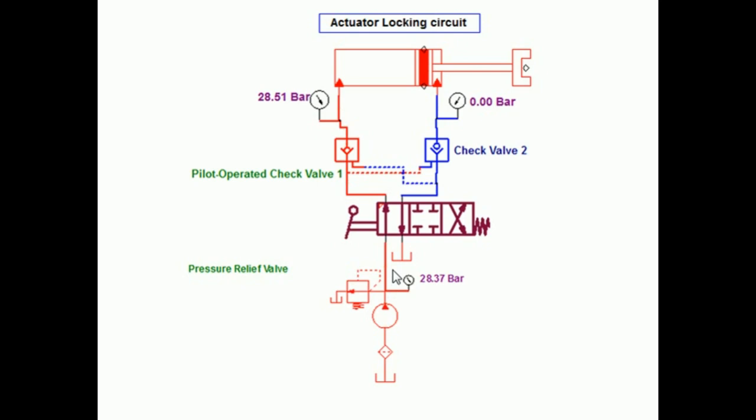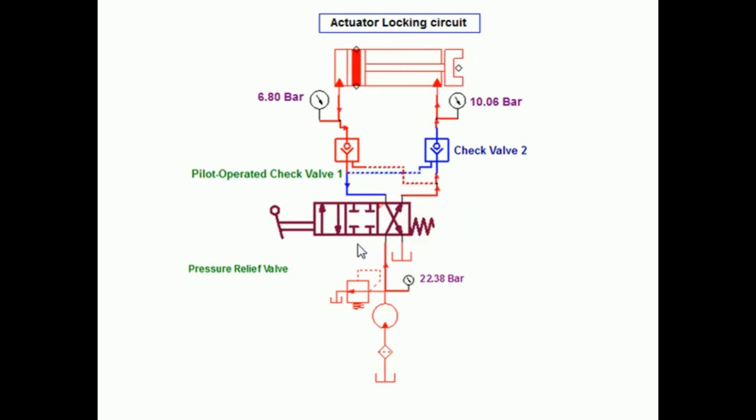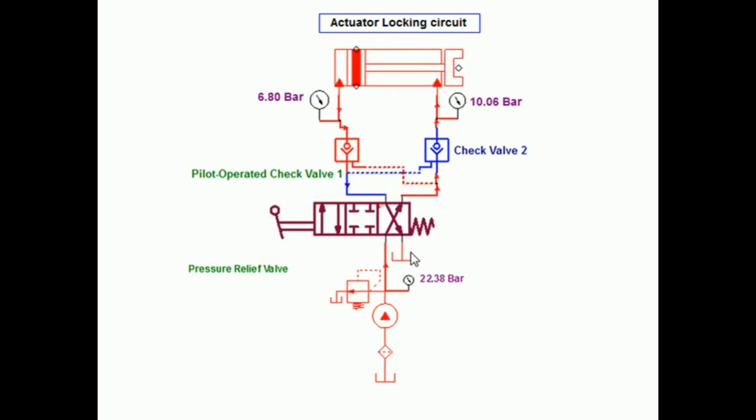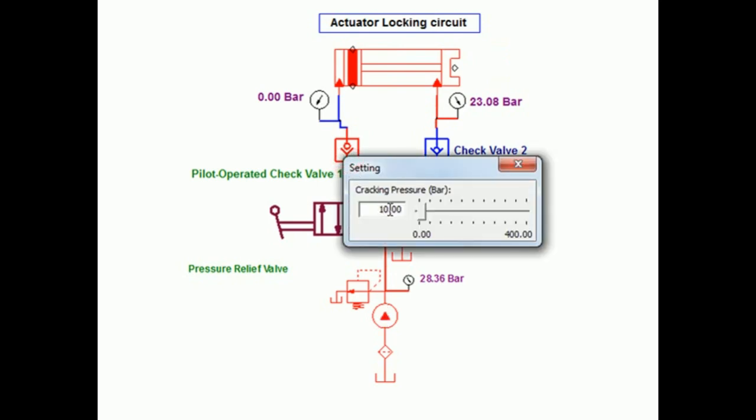Again for the retraction purpose, I need to actuate the third position so that fluid passes from the pump to the rod side end of the cylinder. The check valves get opened because of pilot pressure, and fluid is returned to the reservoir from the blank end of the cylinder.